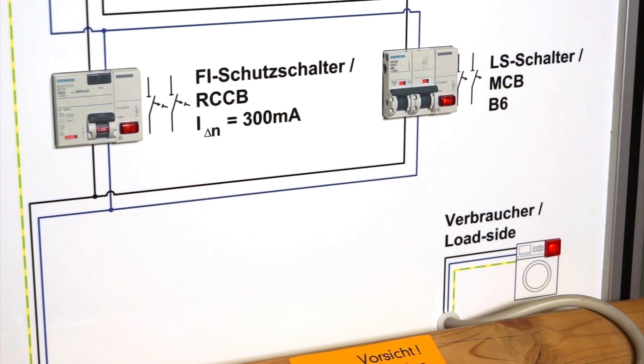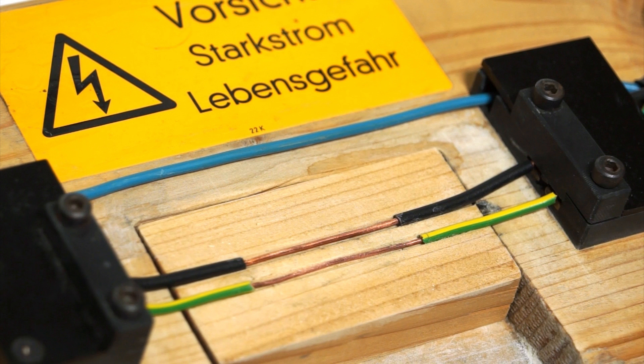This simulation shows how RCCBs can be used to provide fire protection. For this, the rated residual current must not exceed 300 milliampere. Our example shows an insulation fault between two cables.